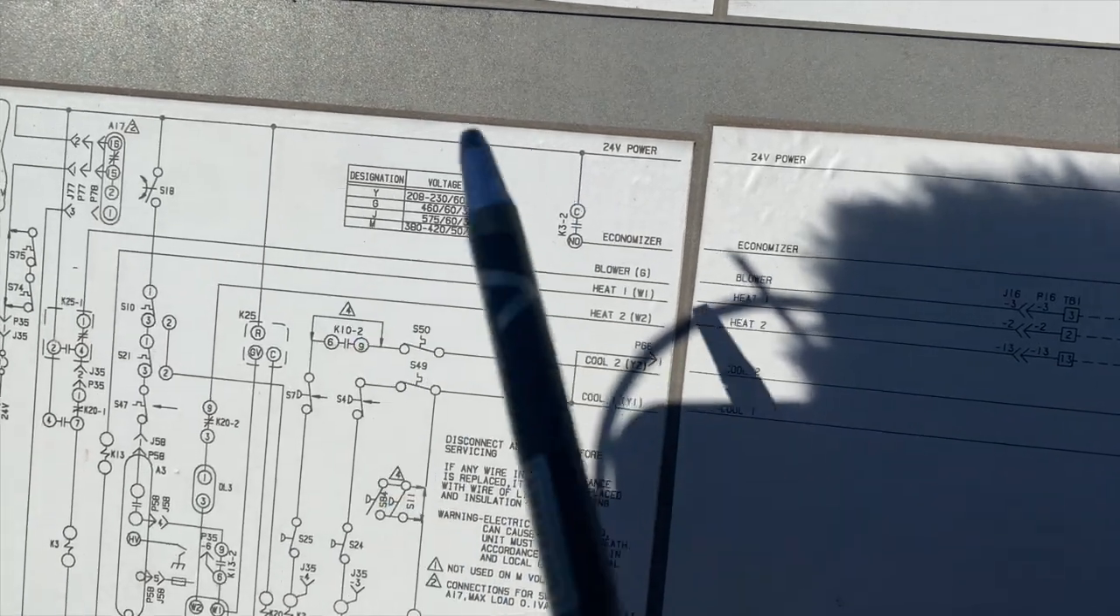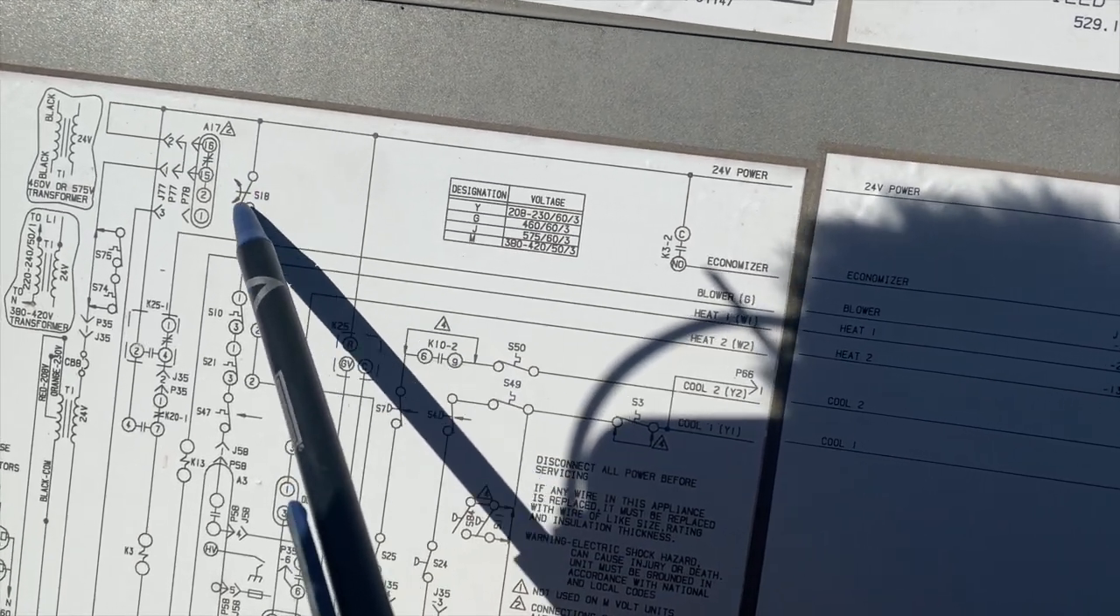I've been looking at the schematic here just to make sure that I know how this works because every manufacturer is a little bit different. Basically this is our 24 volts coming in right here, we have S18 which is our centrifugal switch. It's going to go through S10 which is our primary high limit switch. These are all just limit switches. Then it's going to go into this guy right here, which is our ignition module.